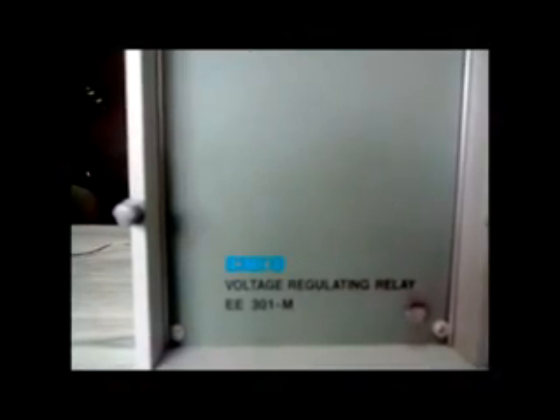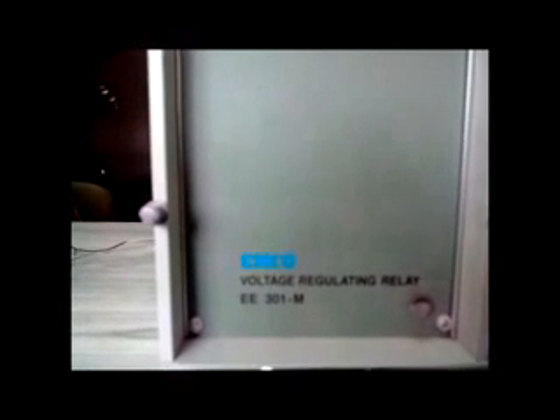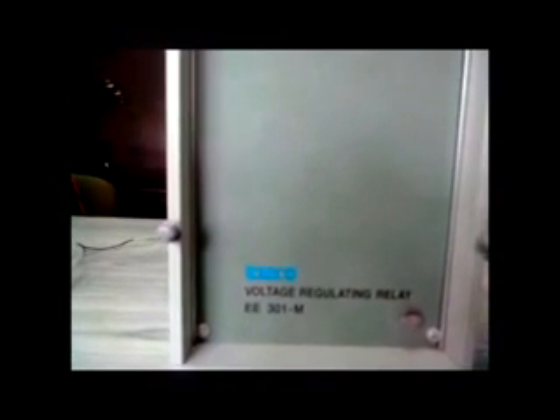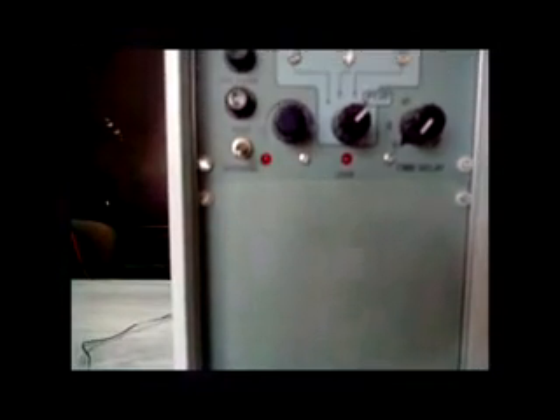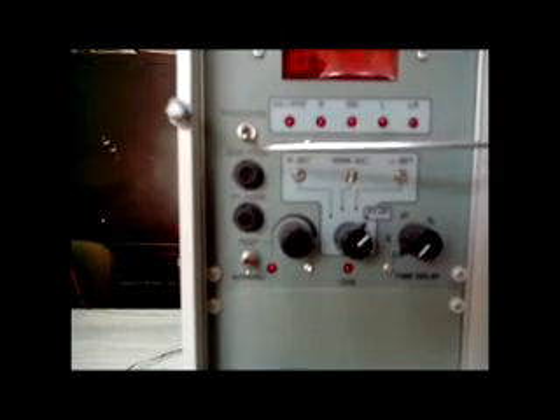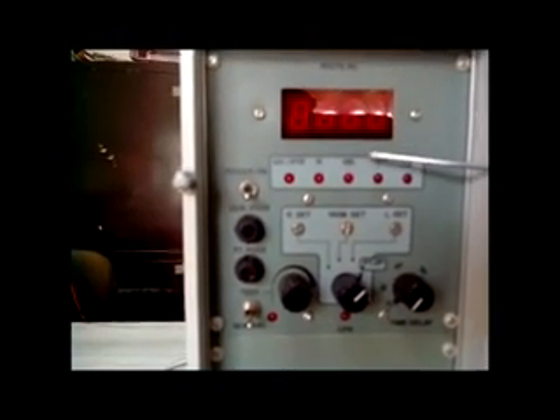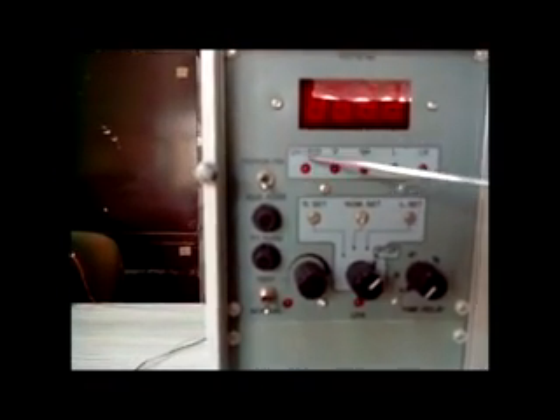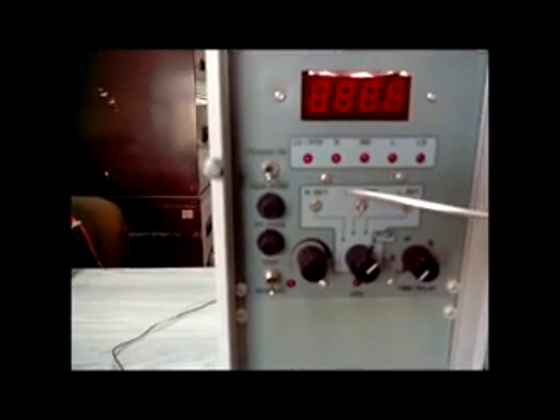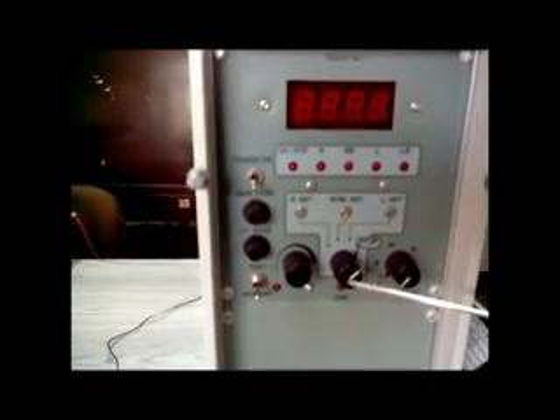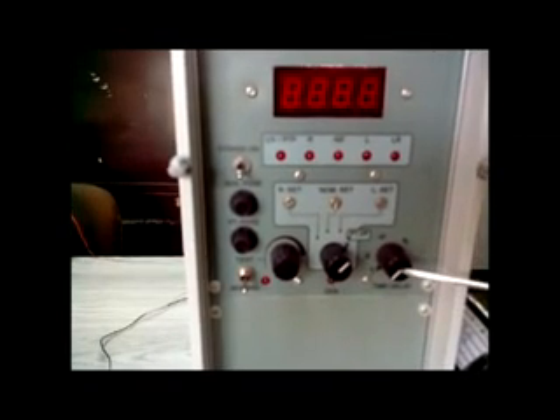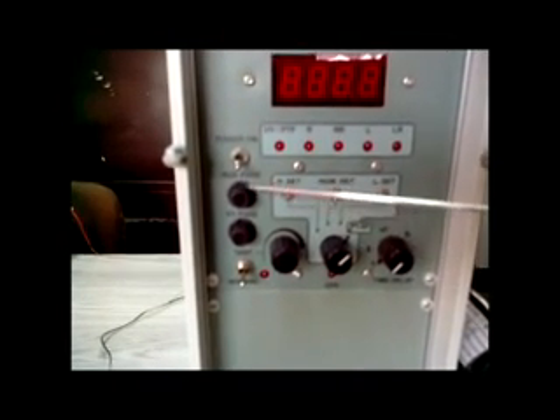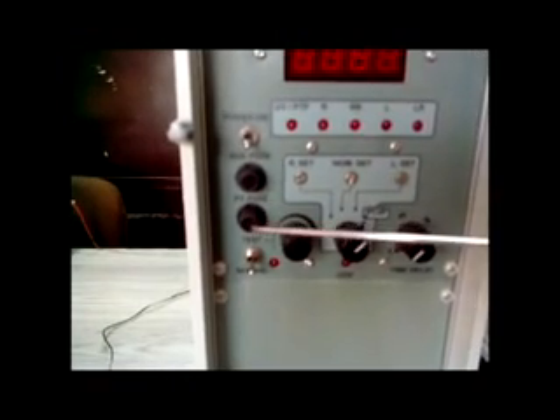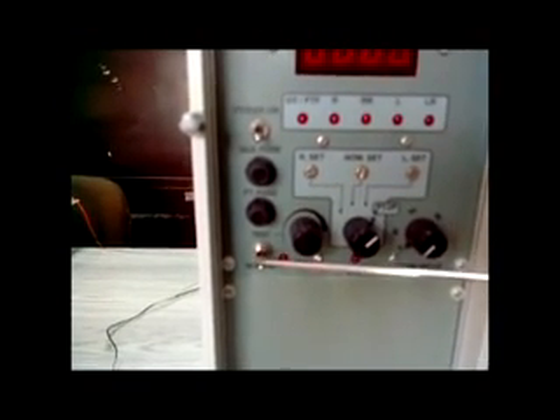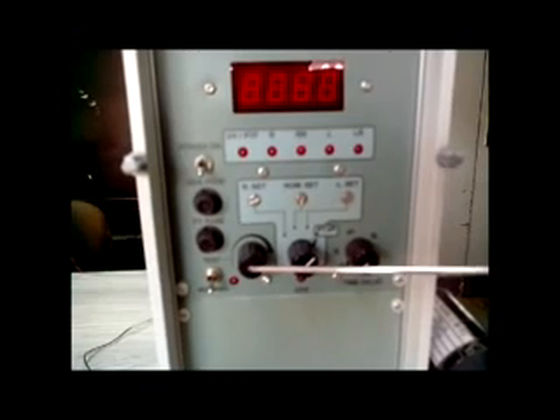AVR EE301M. Demonstration of Automatic Voltage Regulating Relay EE301M. Now you can see the front panel of the regulating relay. There is one power on-off switch. For voltage display, a 4-digit display. For command indication, LEDs are there. For set mode, there are 3 pots and 1 selector switch. For the delay set, there is a set pot for setting. For auxiliary and PT protection, auxiliary and PT fuses are available. For test or nominal operation, there is 1 switch and knob.